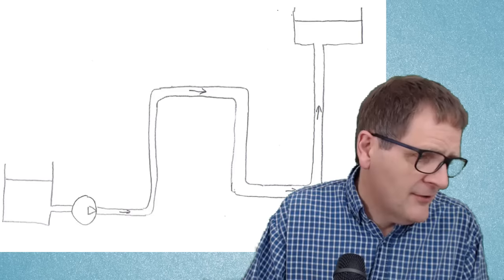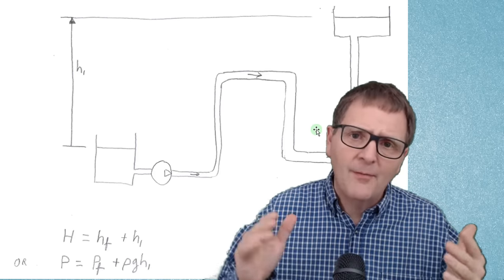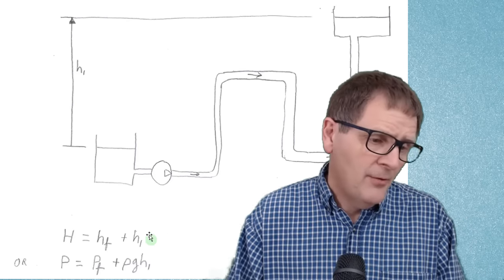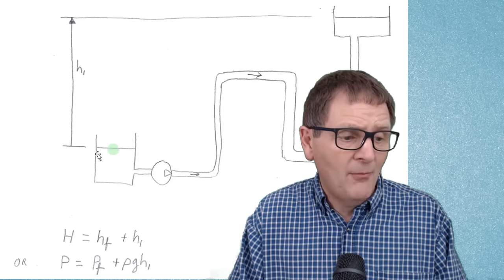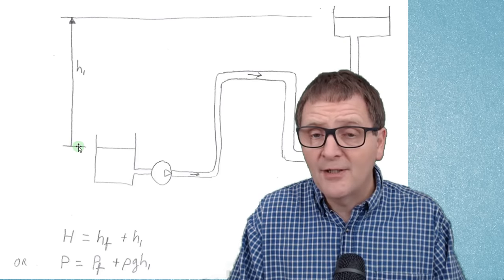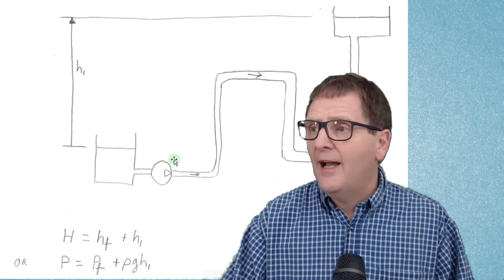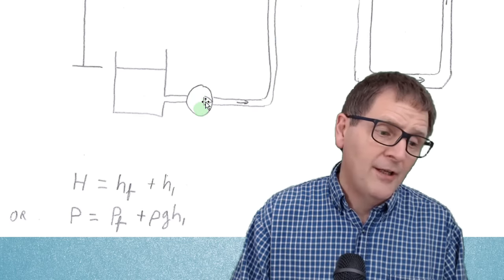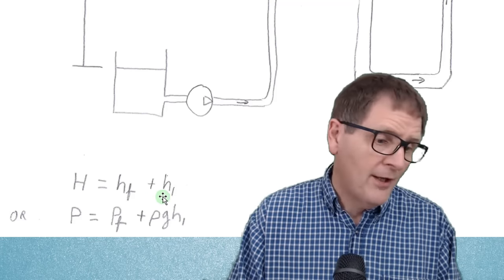Moving on, let's look at what pressure or head you're going to require to drive the fluid along the pipe. Typically for a system like this, the tank where you're taking the fluid is at one level and you're pumping the fluid up to a higher level. The head difference between the two tanks is H1. For a given flow rate along that pipe there will also be a friction head loss, and the total head the pump has to deliver is H = HF + H1.